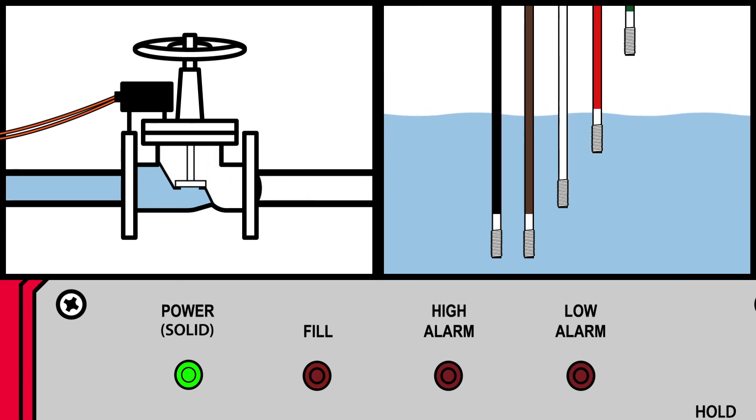If the water drops below the brown rod, the low-alarm LED turns on with the fill LED. If the water rises too high and touches the green rod, the high alarm activates.